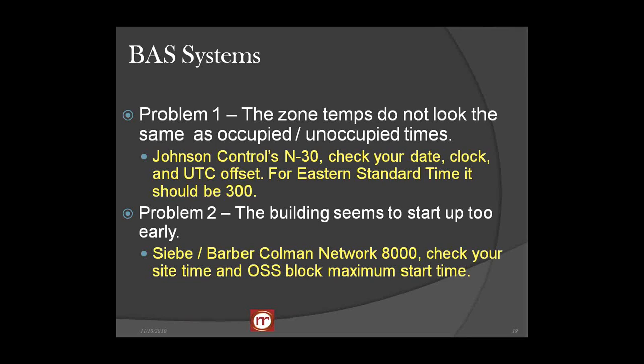And if you have a Barber Colman Network 8000, you might want to check your time and check your OSS block, optimum start stop. What is the maximum time that you will allow the system to back up in cold weather? We found that typically you had an hour or 2 hours. Somebody had changed hours, and we had as much as 10 hours on some schools, and you'd have schools starting up for a 5 o'clock startup, 8 o'clock the previous night. So need to watch that.